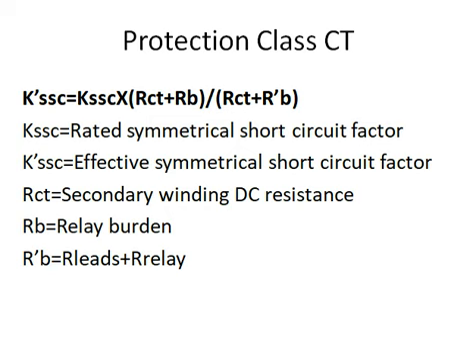In this formula, Rct is the CT secondary winding resistance at 20 degrees centigrade, Rb is the relay burden, and Rb_dash is the lead resistance plus the relay resistance.